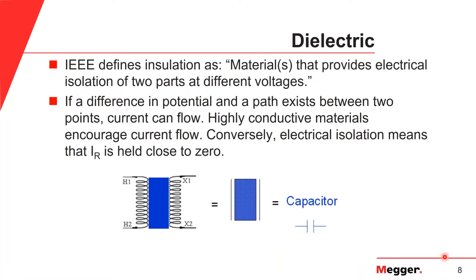IEEE defines insulation as a material or system of materials that provides electrical isolation of two parts at different voltages. If both a difference in potential and a path exists between two points, current can flow. Highly conductive materials placed between two such points will promote current flow, while a dielectric will restrict real current flow. So electrical isolation means that resistive current is held close to zero, and this behavior is very effectively modeled by the use of a capacitor.